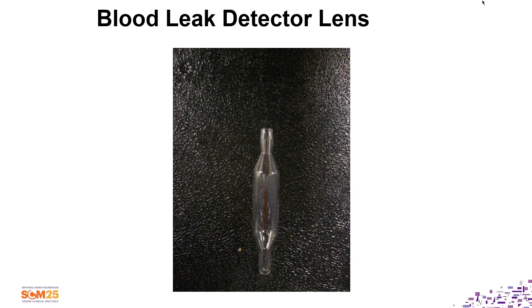Know that the blood sensitivity of this is it'll pick up 0.35 ml. That's how sensitive that detector is, 0.35 ml of blood going through that fluid. And just as an FYI, the level detector denotes 0.05 ml of air into that chamber. So will microbubbles go through that level detector? Yes, it will. There is no such thing as an absolute air detector in our system. It's 0.05 ml is its sensitivity.